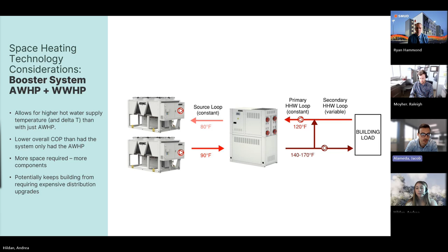So if you go to the next slide, this slide shows that same concept of the booster system, but this time on a much larger scale. And like I mentioned before, this system is called a cascade system, and it can make a lot of sense specifically for campuses. If your entire campus is designed around 180-degree heating water, switching over to 130 heating water could be a ton of work. So using a large-scale cascade system to switch that system over to 165-degree water instead of 130 could save you from the vast majority of upgrades that would be needed at the building level.